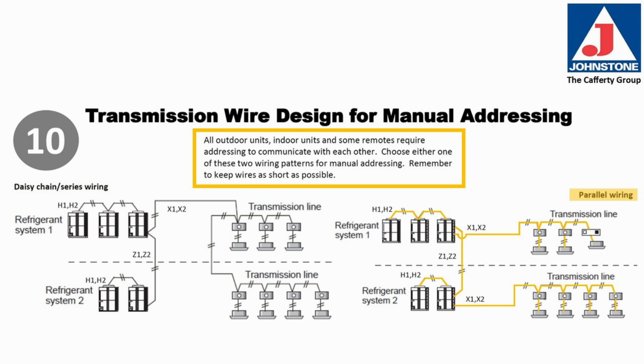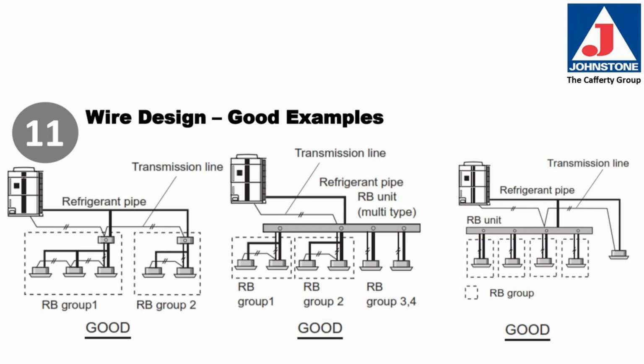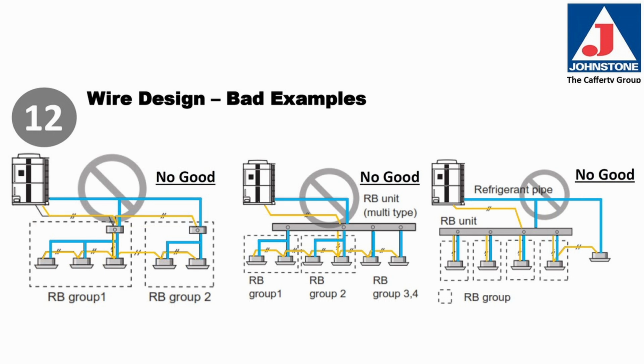On the right, you see an example of a parallel wiring system where the bottom system runs a transmission line to the indoor units connected to it. Top system runs a transmission line to the indoor units connected to it, and then the two outdoors are communicating as well. Here are some examples of a good transmission wire design. Here are some examples of bad transmission wire design. Let's talk about what makes a good and a bad transmission wire layout.